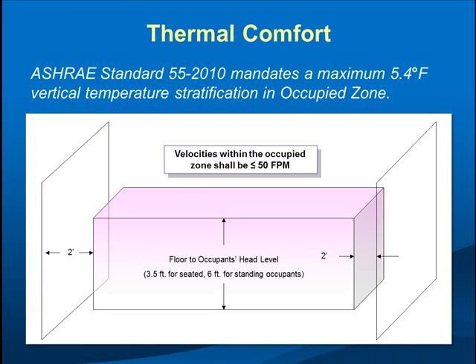The occupied zone is defined in ASHRAE Standard 55 and several other standards. It is the space from the floor to six feet (or three and a half feet for seated occupants) and within two feet of the walls. In that space, air velocity should be less than 50 feet per minute at all points. Note that the occupied zone does not extend all the way to the wall — sitting next to a window is technically outside the comfort zone.